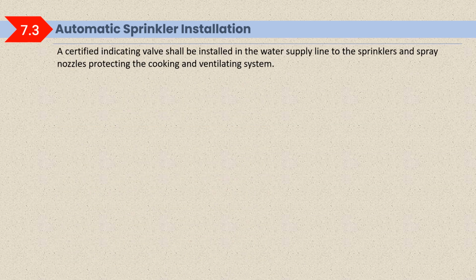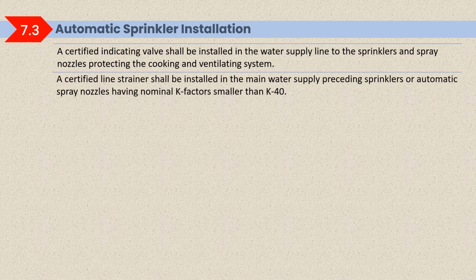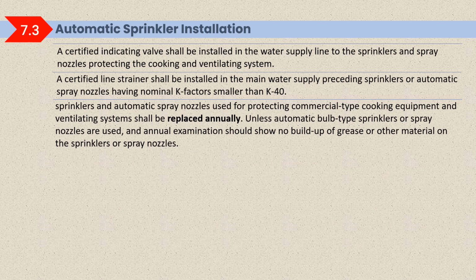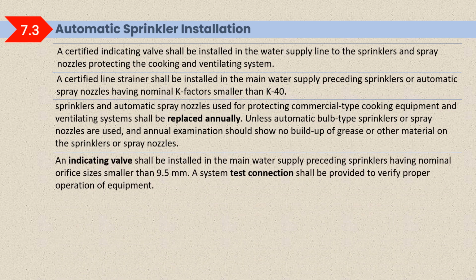A certified indicating valve shall be installed in the water supply line to the sprinkler and spray nozzle protecting the cooking and ventilating system. A certified line strainer shall be installed in the main water supply preceding sprinkler or automatic spray nozzle having nominal K factor smaller than K40. Sprinkler and automatic spray nozzles used for protecting commercial type cooking equipment and ventilating systems shall be replaced annually, unless automatic bulb-type sprinklers or spray nozzles are used, and annual examination should show no buildup of grease or other material on the sprinkler or spray nozzles. An indicating valve shall be installed in the main water supply preceding sprinklers having nominal orifice size smaller than 9.5 mm. A system test connection shall be provided to verify proper operation of equipment.